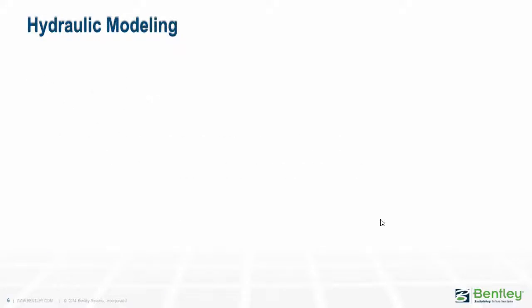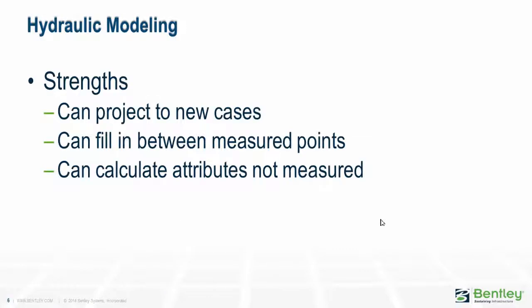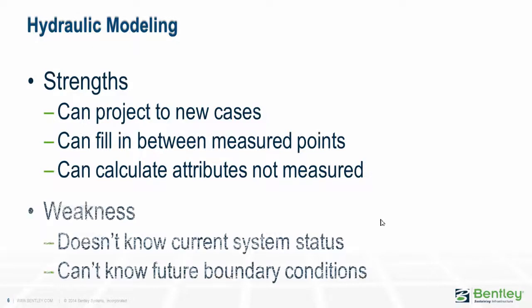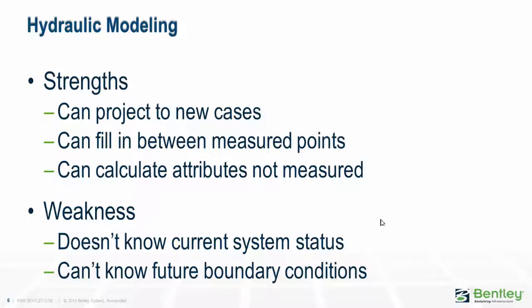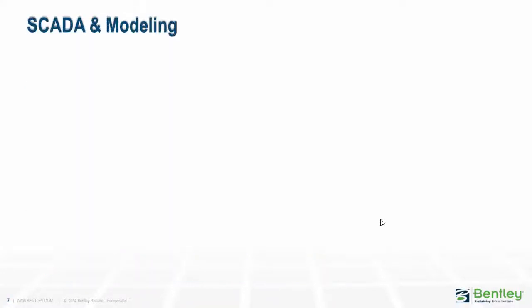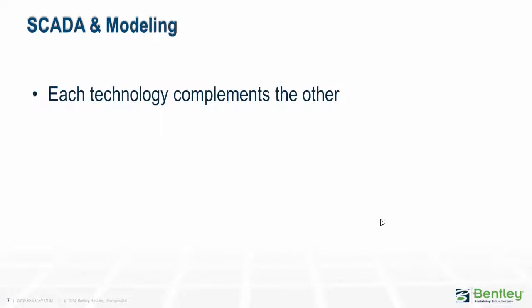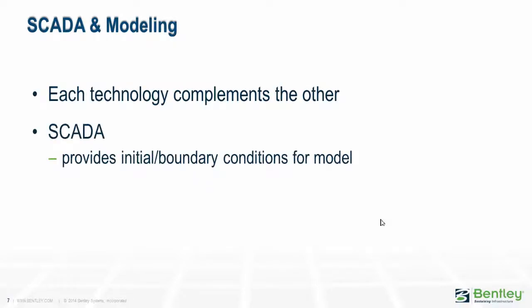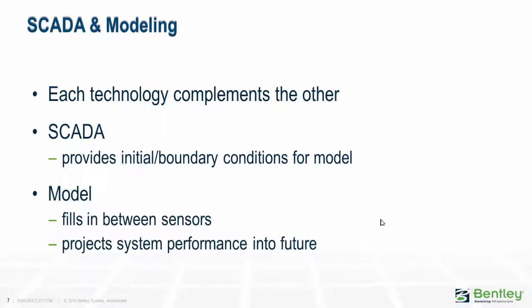With hydraulic modeling we can project out to new cases, fill in between measured data points, and calculate attributes not measured by the SCADA system. The problem with models is they don't know the current status of the system or boundary conditions or historical measured values. But when we link SCADA systems with modeling we have real power. Each technology complements the other. SCADA can provide initial and boundary conditions for the model, and the model can fill in between sensors and project what's going to happen into the future for what-if questions.